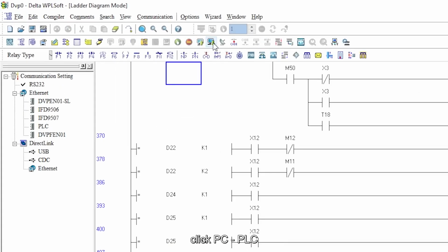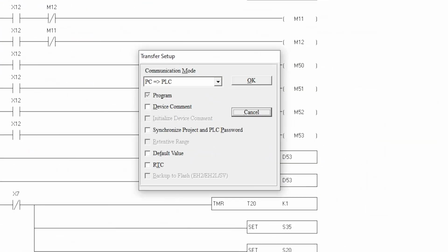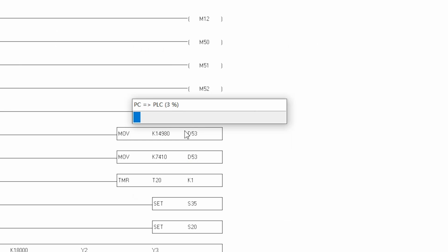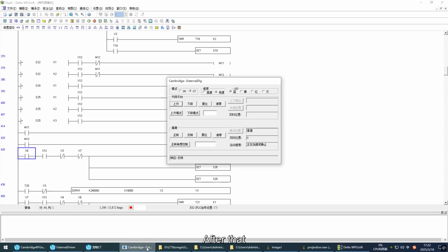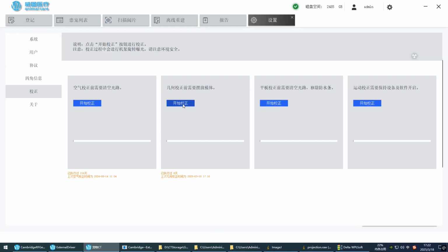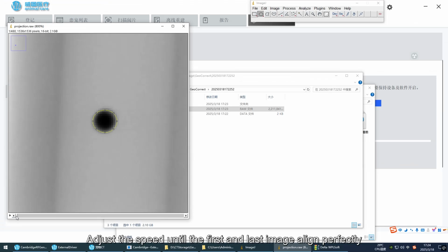11. Adjust Image 3. After adjusting the values, click PC, PLC. Then click OK and run program. After that, you need to go back to the rack control and reselect the high and low speeds. Then, proceed with the geometric calibration again. 12. Adjustment complete example. Adjust the speed until the first and last image align perfectly, then the process is complete.